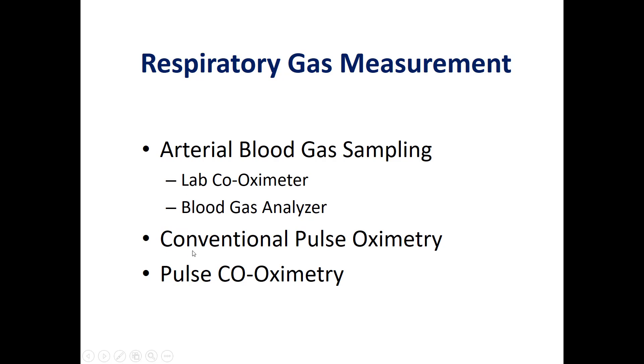A replacement for this is through the use of a pulse oximeter, or it helps as a first-line screening. The pulse oximeter allows us to measure non-invasively. We have the conventional pulse oximeter — the first and second generation — and we also have the pulse co-oximeter, which is the third generation and is in reality more of a true replacement for the lab co-oximeter, where we measure all types of hemoglobin, like methemoglobin and carboxyhemoglobin, which were unavailable in the second generation or conventional pulse oximeter.